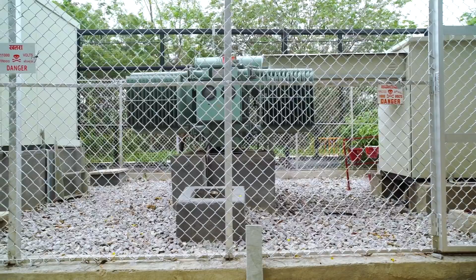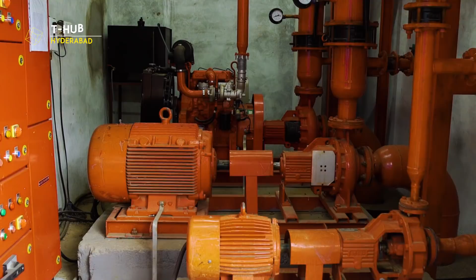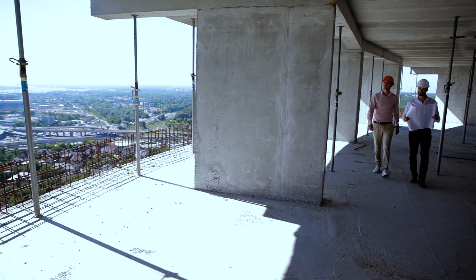The major electrical components in a building are transformers, motors, and the distribution system. So requirements are given that the transformer should have this minimum efficiency, motors should have this minimum efficiency, and there are permitted losses in the electrical distribution system. If there are buildings like hospitals which have a requirement for hot water, then we can save a lot of energy in hot water by either utilizing waste heat or by utilizing a solar hot water system. Some requirements are given in this section on how we can improve the efficiency of the boilers or reduce our energy consumption by using waste heat or solar energy.